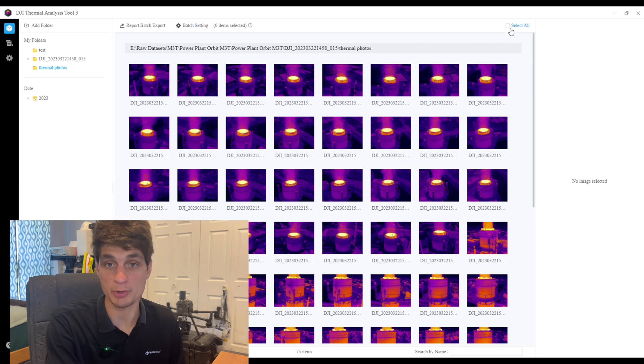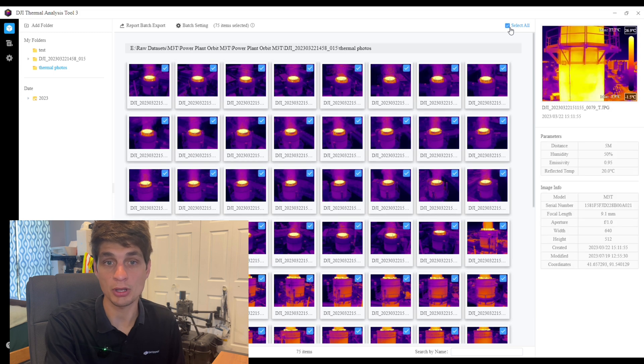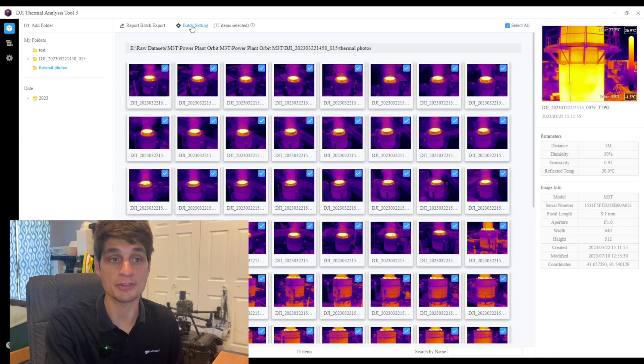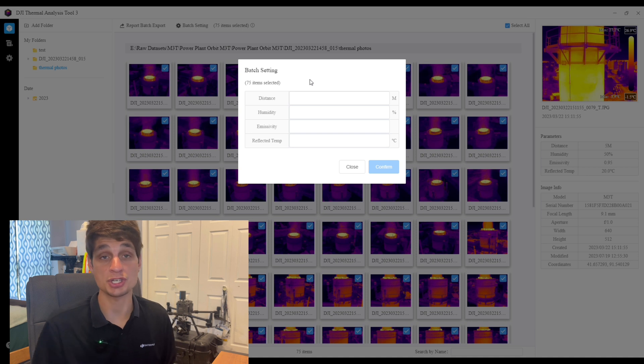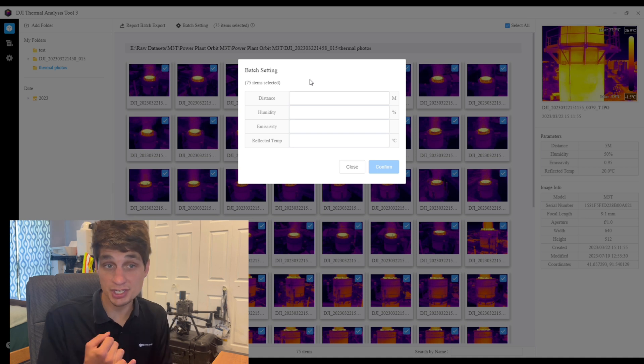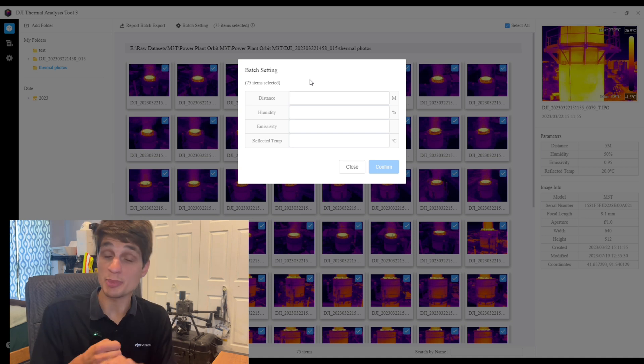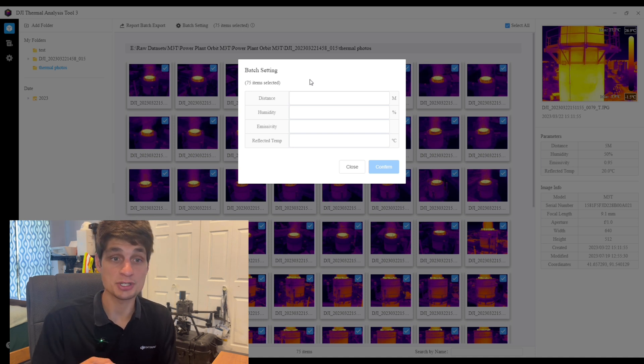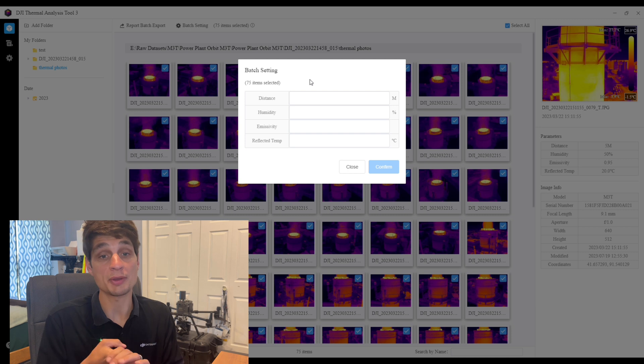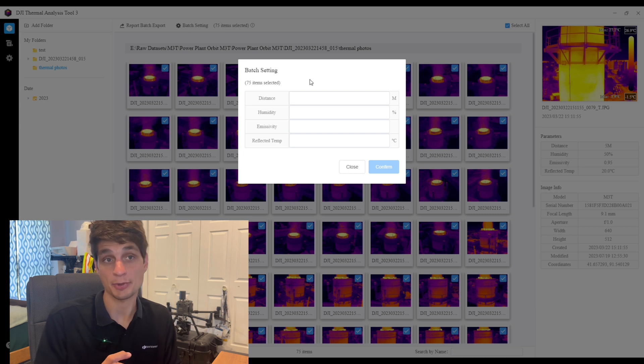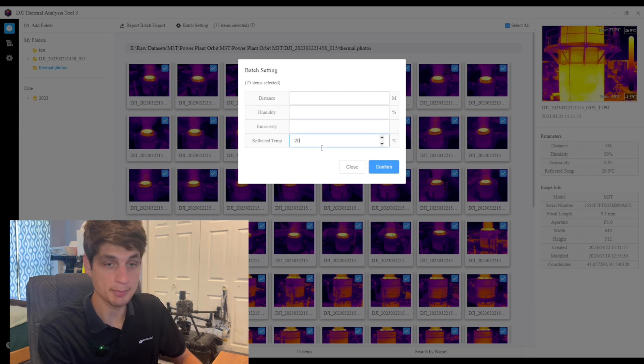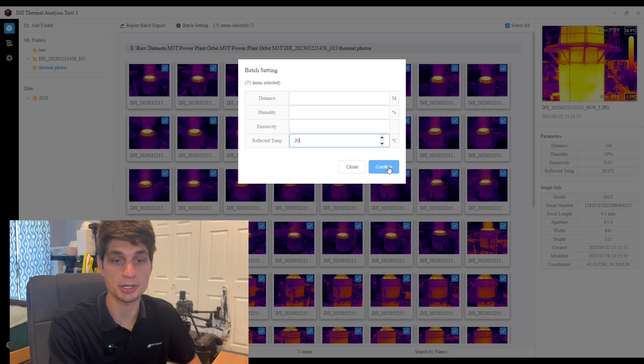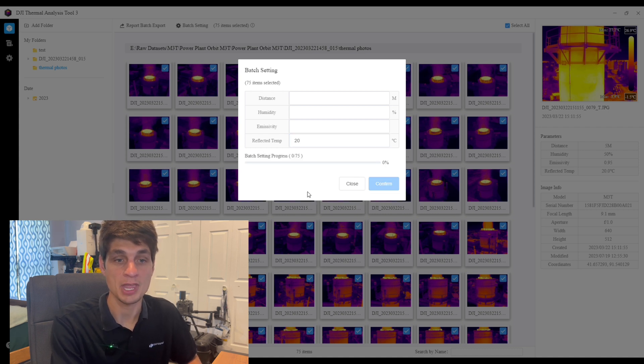Select one or more images, I'm going to go ahead and select all, and now I have the ability of selecting batch setting and changing the distance, humidity percentage, the emissivity, or the reflected temp. I'm going to go ahead and type in a reflected temp of 20 degrees celsius and confirm.